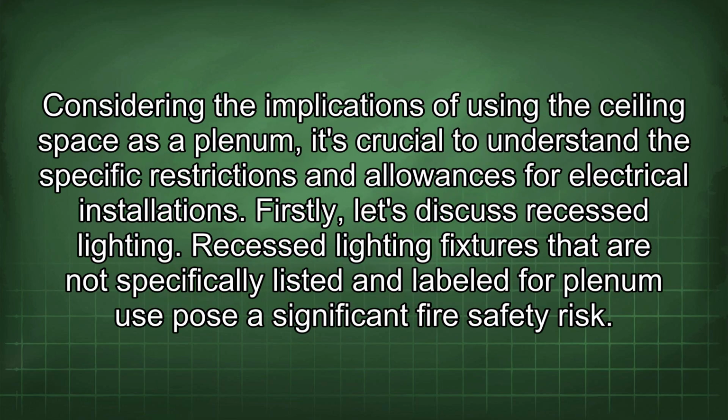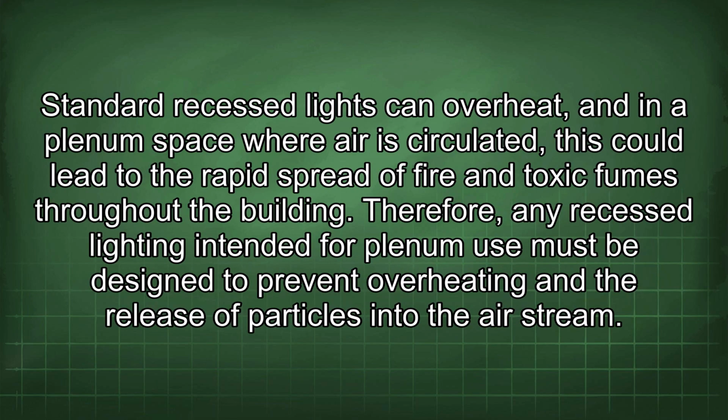Considering the implications of using the ceiling space as a plenum, it's crucial to understand the specific restrictions and allowances for electrical installations. Firstly, let's discuss recessed lighting. Recessed lighting fixtures that are not specifically listed and labeled for plenum use pose a significant fire safety risk. Standard recessed lights can overheat, and in a plenum space where air is circulated, this could lead to the rapid spread of fire and toxic fumes throughout the building.